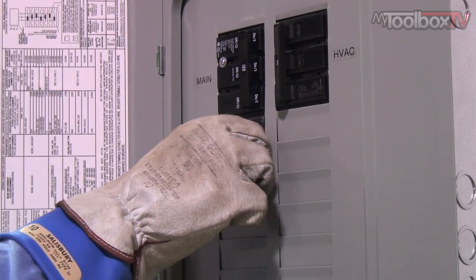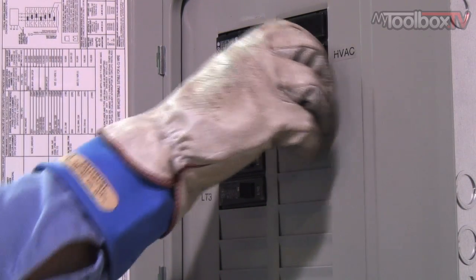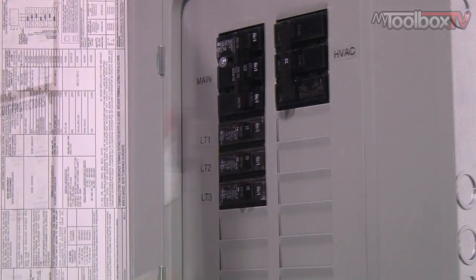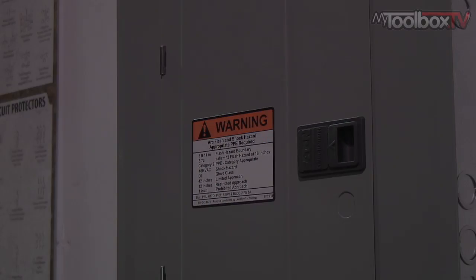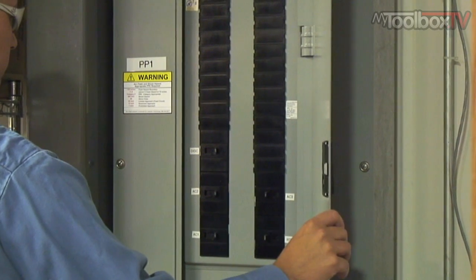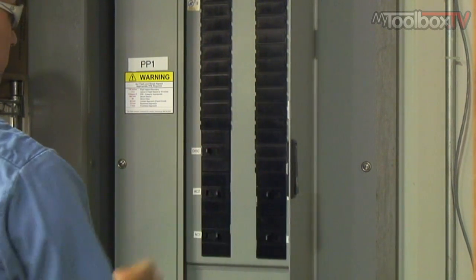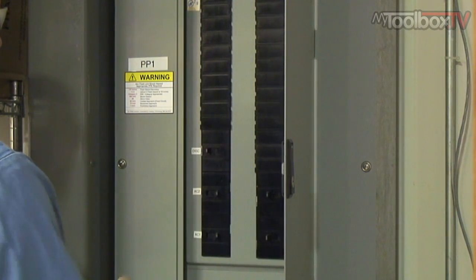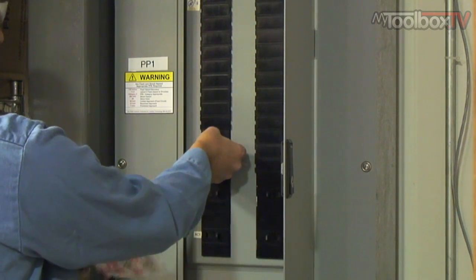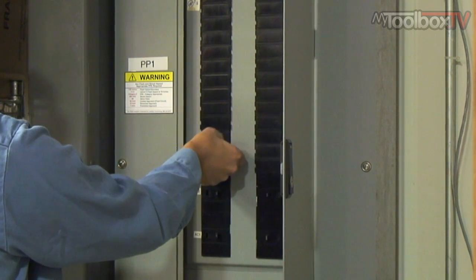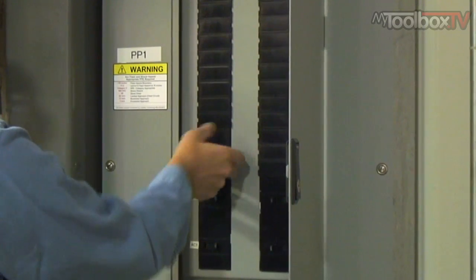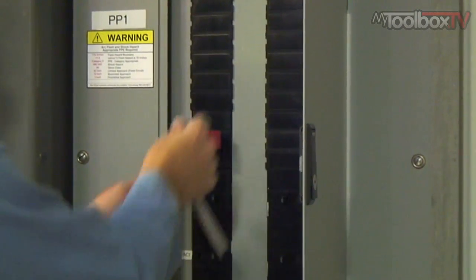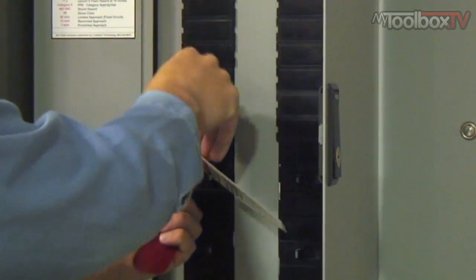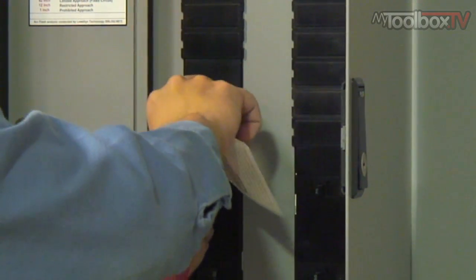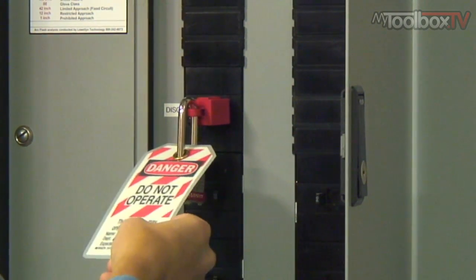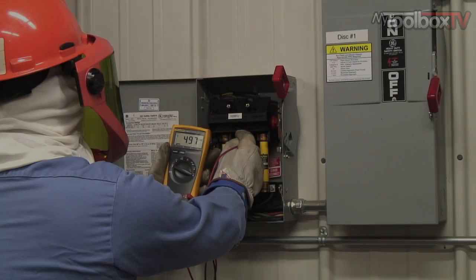He's turning off all the loads that this panel is providing power for prior to turning off the main breaker that feeds the panel. He's located the breaker that feeds that panel and he's shutting it off. Now he's putting on the lockout tagout device on that circuit breaker so that nobody turns that on while he's working. It's important that you follow your company's lockout tagout policy, not necessarily exactly as we've shown in the video. It's important that you make that distinction.